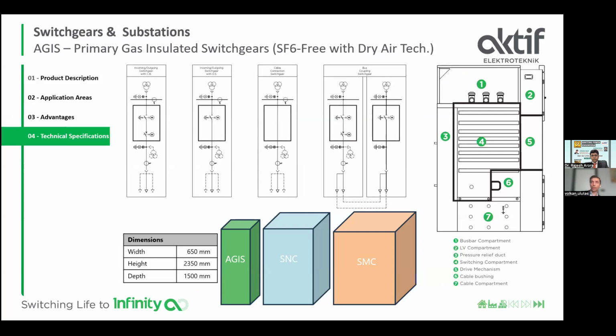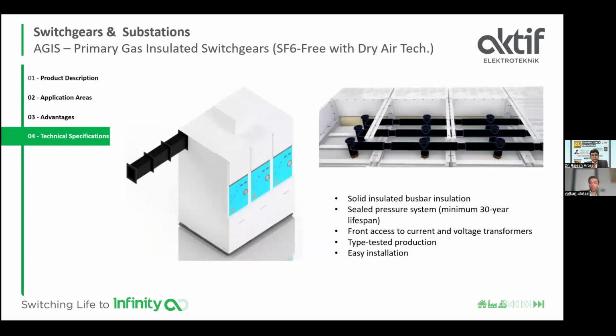You can see the different combinations of the applications, and the disconnector switch or the circuit breaker is located inside the tank with pressure. The footprint is very small compared to air insulated primary switchgears. The width is 650 millimeters. We have solid insulated busbar insulation and a sealed pressure system with minimum 30 years lifespan, and a front accessibility option to the current transformer, voltage transformer, cable connection points, and busbar structure. Whenever you want, you can reach each of them separately. And type tested production and easy installation are supplied.